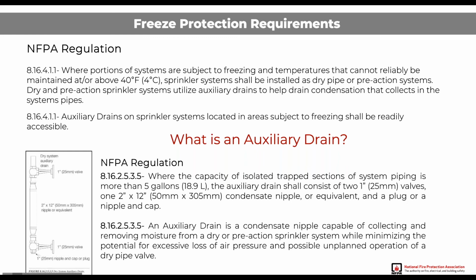Since that system doesn't have any water in it in its usual state, you have to accommodate for if any water gets into it. This could be through condensation in the air. We all know there's water molecules in the air, and that air can carry, and what we're worried about is those water molecules freezing and locating anywhere near a sprinkler head, or accumulating and freezing and breaking pipe. So you have to have accommodations to collect any moisture in a dry or pre-action system, and they make these products called auxiliary drains. And they're very simple devices.